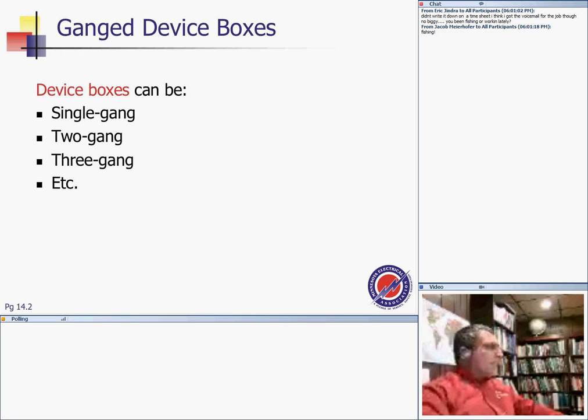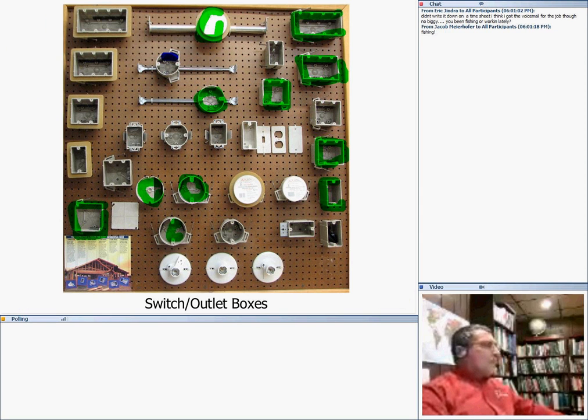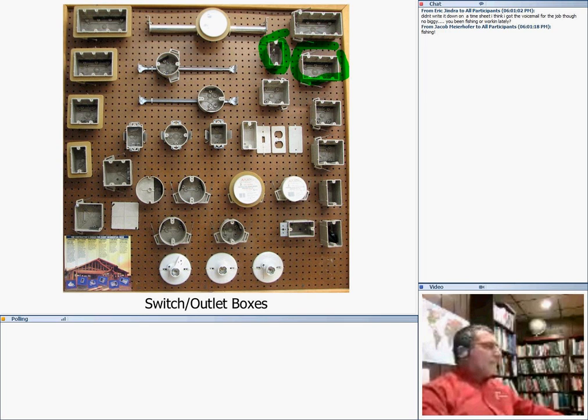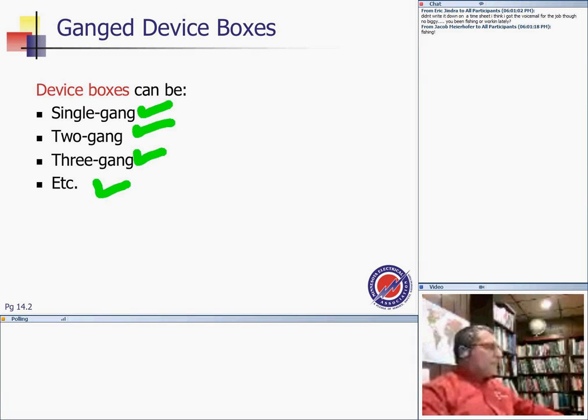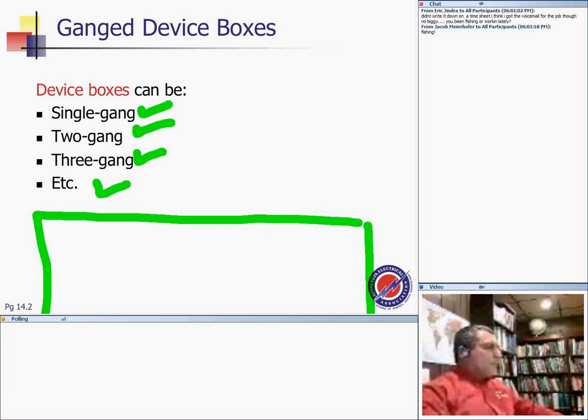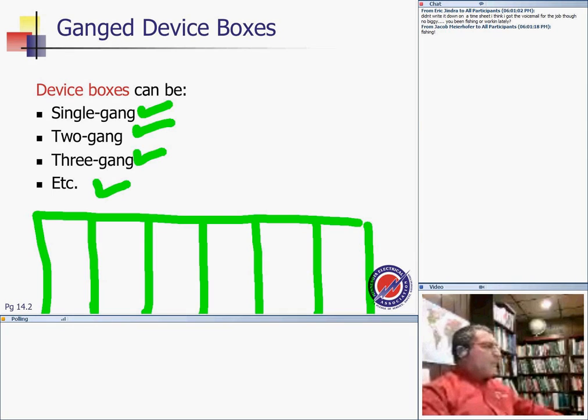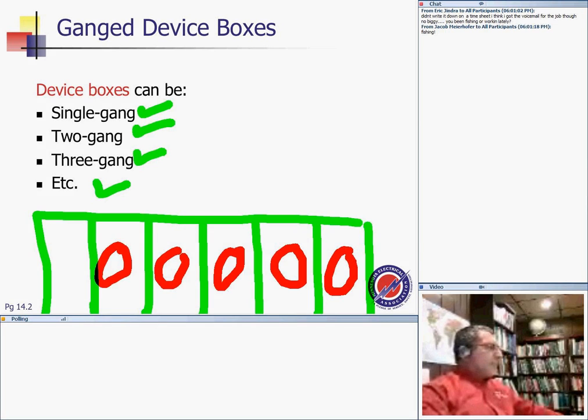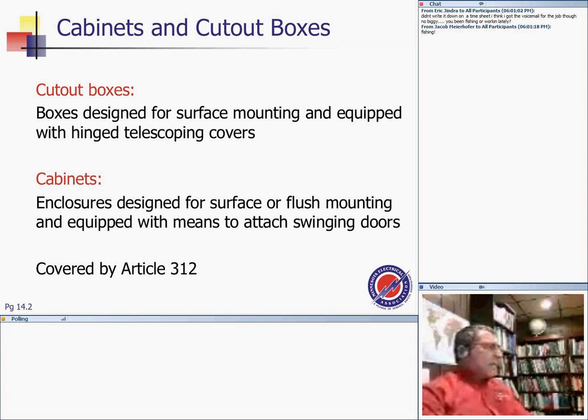Okay, device boxes. You can have them single gang, 2 gang, 3 gang, and up to what? 8 gangs and more, even, if you support them right. So if you're not familiar with ganging, guys, this is a 6-gang device box. This is a 3-gang device, a 4-gang device. As you can see, you can put device 1, 2, 3, 4. So 2-gang devices here, depending on how many devices you can fit in that box. So I put in my devices; you don't have to split them, but I'm just showing you. 1, 2, 3, 4, 5, 6. I can put 6 devices in this gangable metallic box, and each one of them will be sitting in this enclosure, and they don't have to be separated. Any questions about gangable boxes and non-gangable boxes?